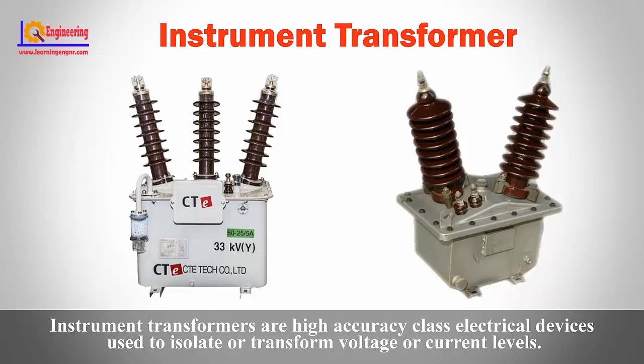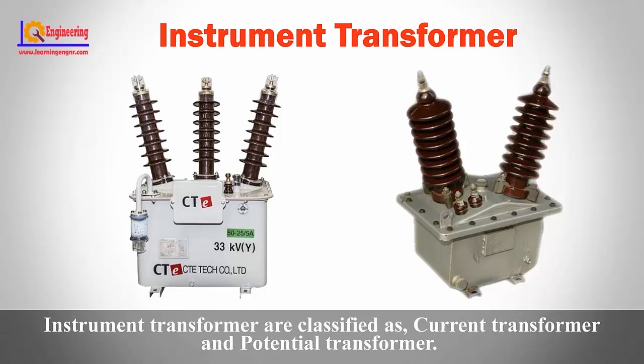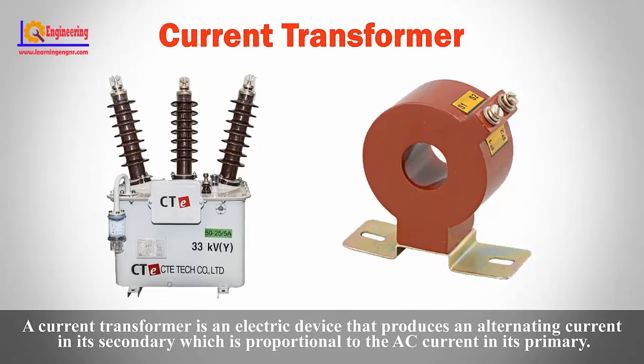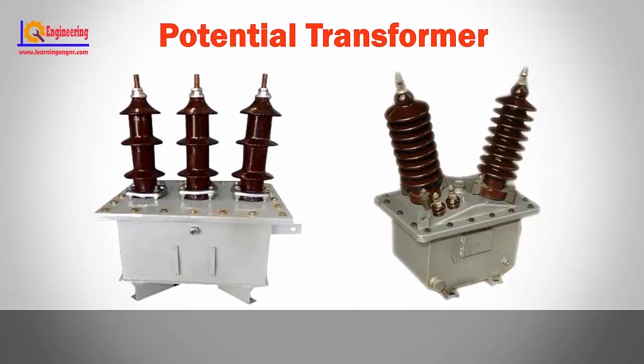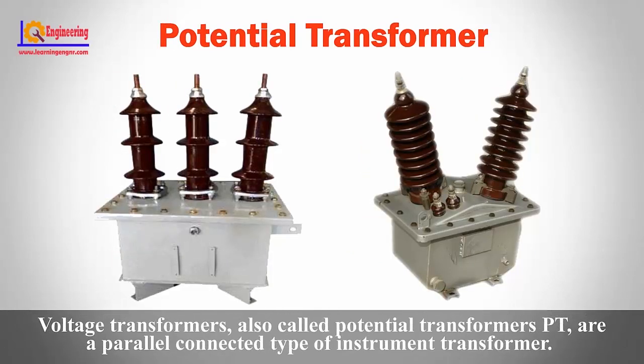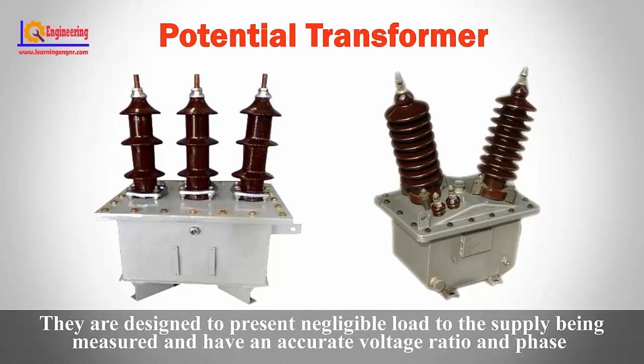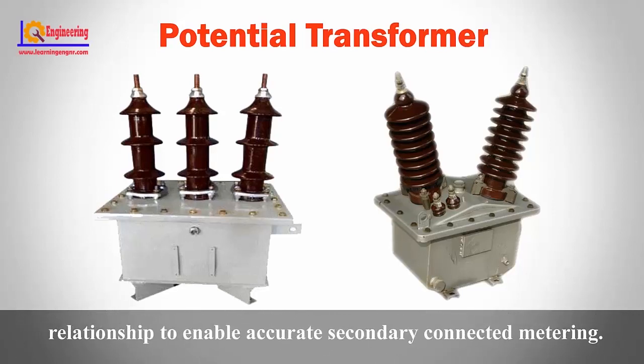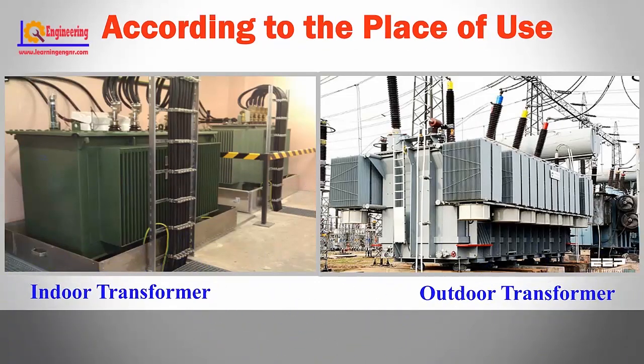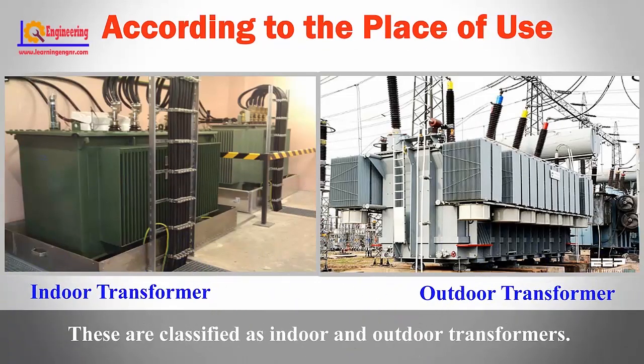Instrument transformers are high-accuracy class electrical devices used to isolate or transform voltage or current levels. They are classified as current transformer and potential transformer. A current transformer is an electrical device that produces an alternating current in its secondary which is proportional to the AC current in its primary. A potential transformer, or PT, also called a voltage transformer, is a parallel-connected type of instrument transformer designed to present negligible load to the supply being measured, with an accurate voltage ratio and phase relationship to enable accurate secondary-connected metering.